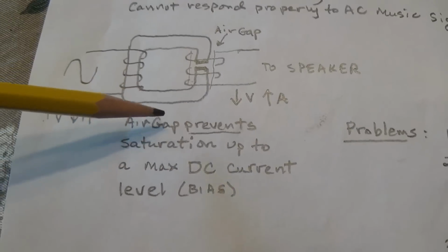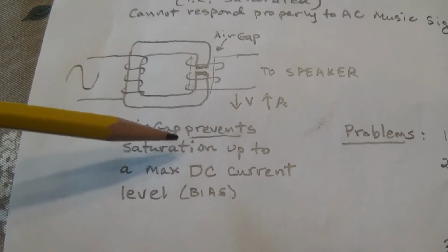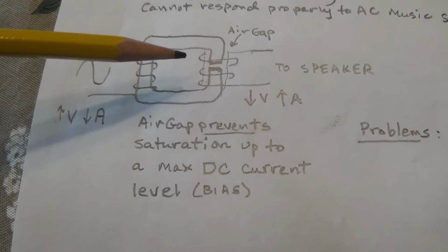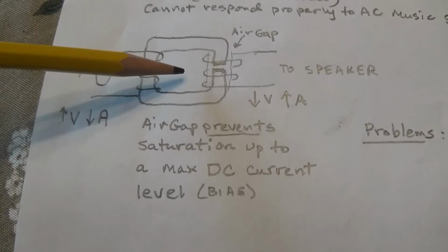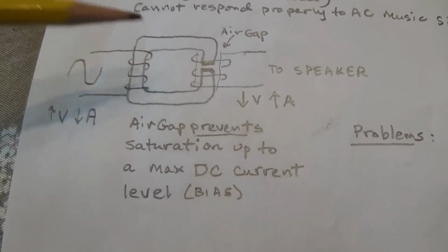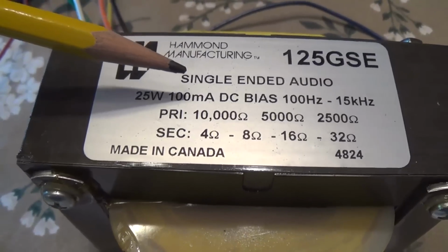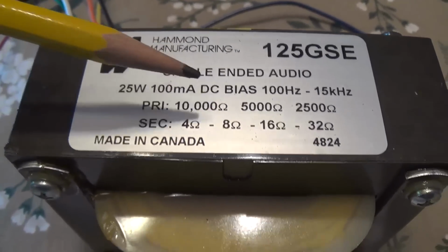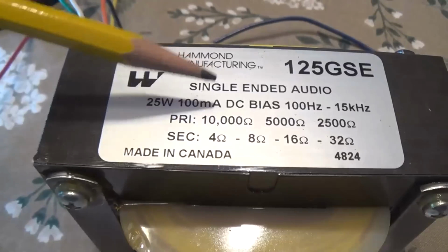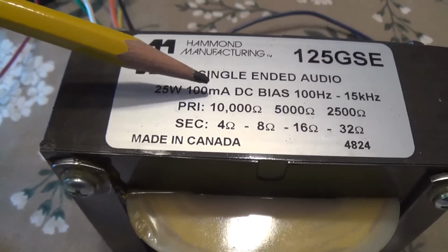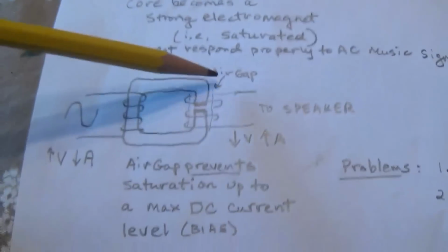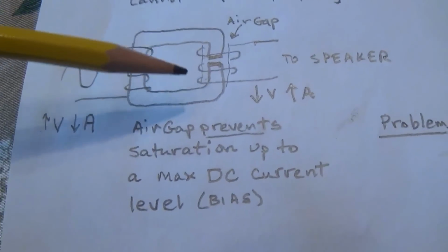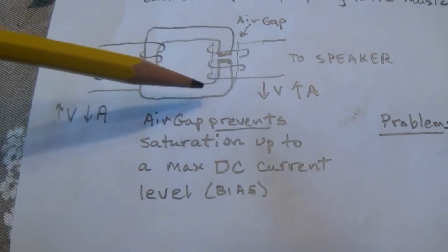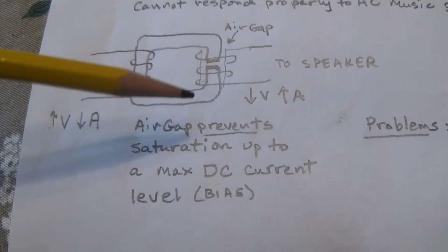So the air gap here prevents saturation up to a maximum DC current level, which will be the bias level of the transformer. We see here that the bias level for our single-ended transformer is around 100 milliamps. Above that point, we're going to start to saturate the core, and we may start to have some issues.